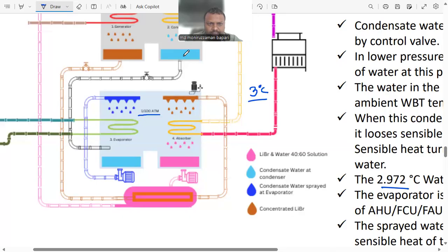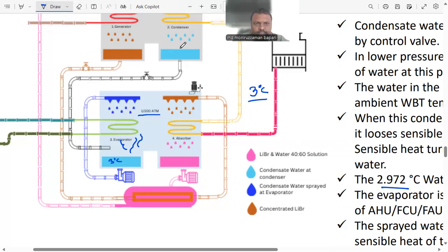Remember the water temperature was higher in the condenser. Now when water comes and drops in here, the temperature of the water will fall down to 3 degrees centigrade, and some of the water will be vaporized. Not the whole water, but some of the water will vaporize because the sensible heat of the water was higher in the condenser. When it comes suddenly to a chamber where the boiling point is 3 degrees centigrade, what happens in lower pressure? Suddenly it becomes 3 degrees centigrade. The water temperature goes down, and some of the water evaporates. Now this water is getting sprayed on top of a heat exchanger.